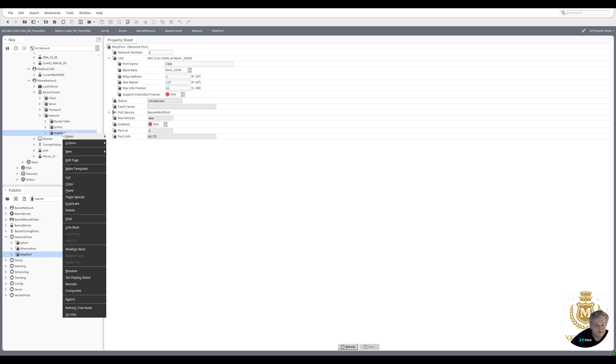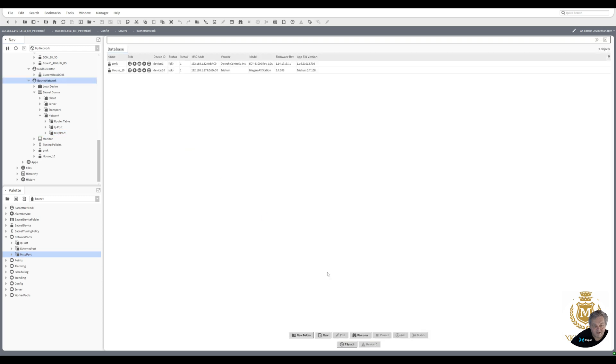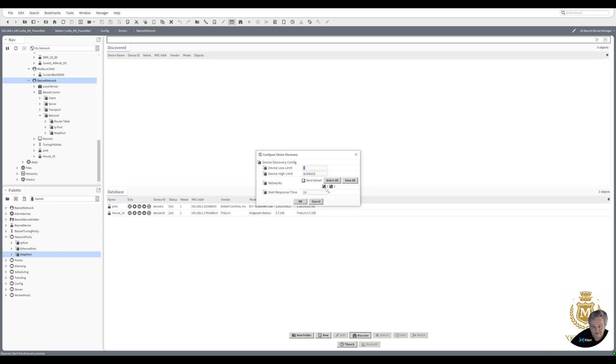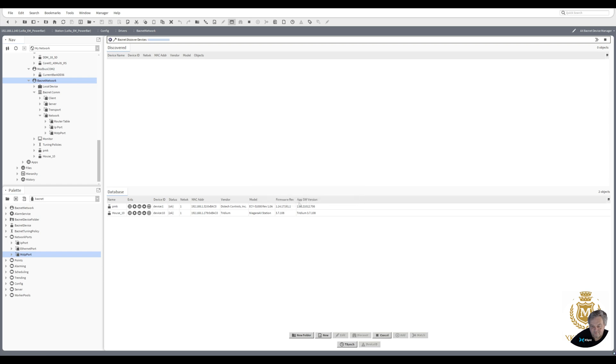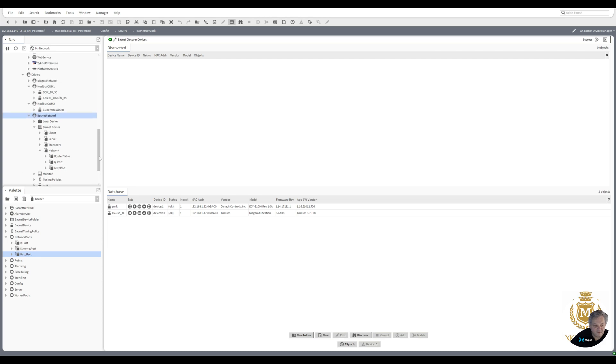Go back to BACnet now. We've got device one and device two, so when I discover it's not showing at the moment. Let's just find out why. Probably not enabled it. Yeah, it's disabled there. So right-click actions enable. That's now come online. Now go back to there and discover. I've got two ports here now, so we know that one's our Ethernet and two is our MSTP. I'm just going to untick one. I don't think I've got anything connected via MSTP and discover. It's discovered nothing, which I would expect. I don't believe I have anything connected.